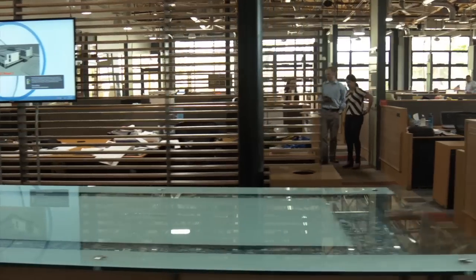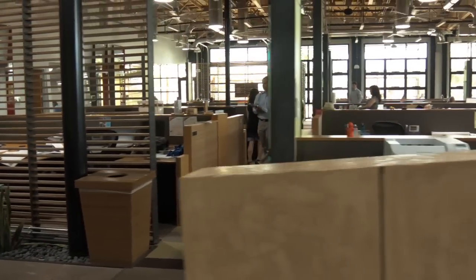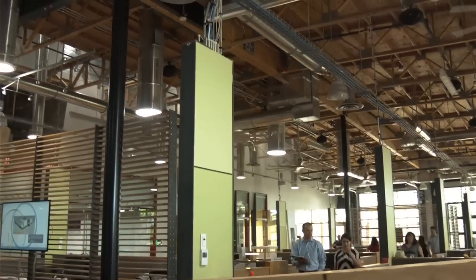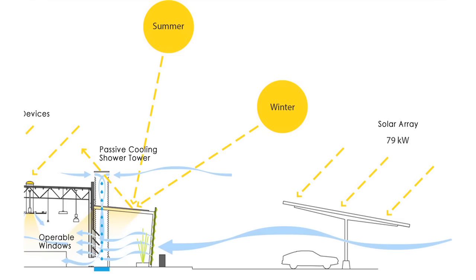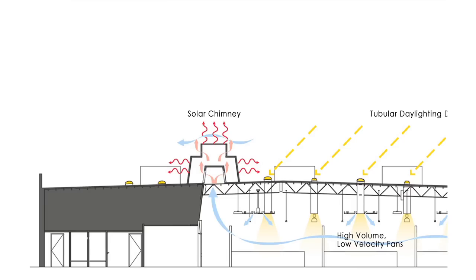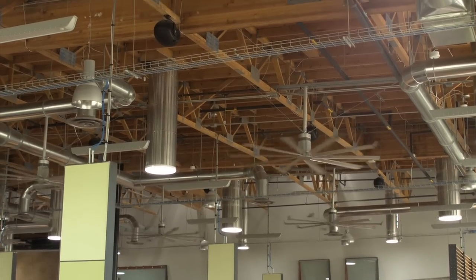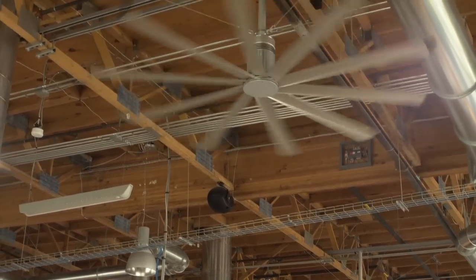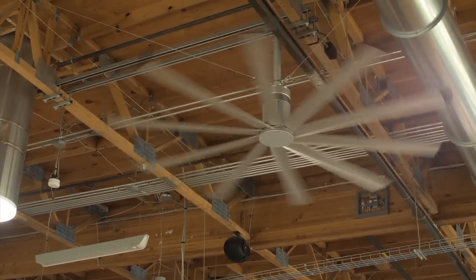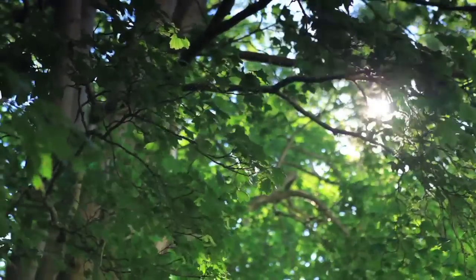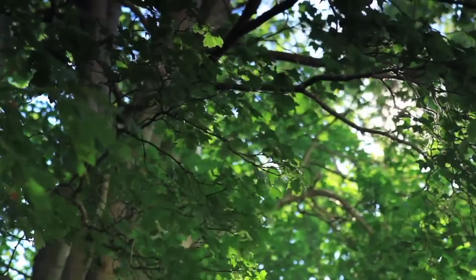Understanding the sequence of operations, you really have to develop how you're going to run the building before you decide what system you can construct and operate. We had to understand that the primary concept was to move air, whether through the windows horizontally and vertically out the solar chimney, or air we were holding in the building and circulating with fan systems that would ramp up slowly as we're trying to cool, and as the temperature rose, they would gradually speed up to maintain that fine cooling point. It's about sensible cooling, how you feel when you're in a nice cool breeze or under a tree on a hot day with the wind blowing. It's much cooler than standing out in the direct sun.